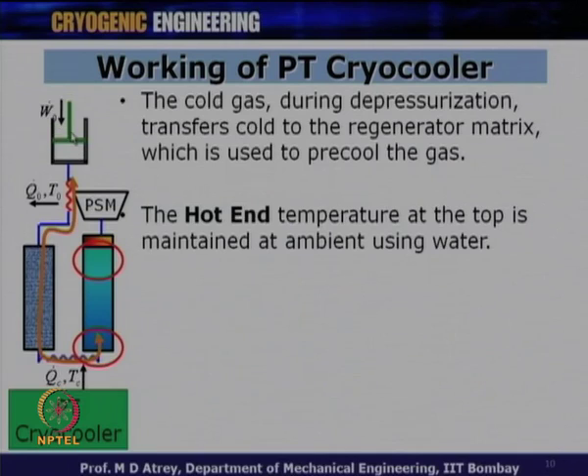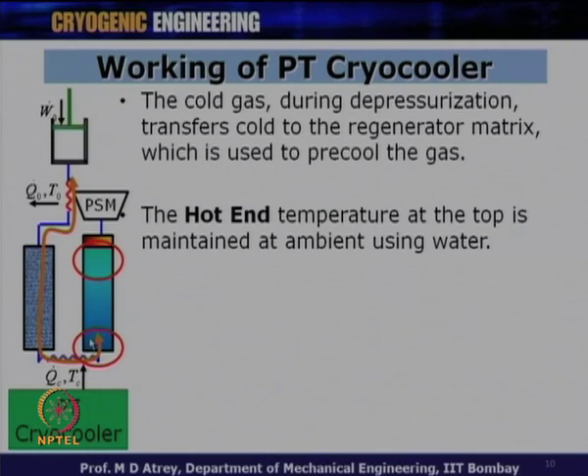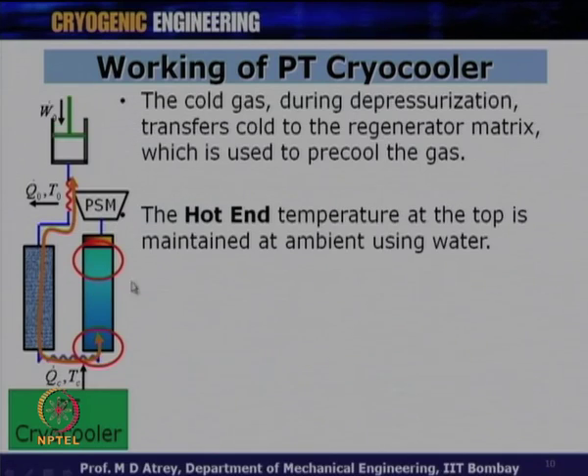This is how the pulse tube cooler works. The pulse tube cooler compresses gas and sets up a temperature gradient across the length of the pulse tube. During depressurization, the gas goes back; the hot end is always maintained at ambient temperature. Thereby, the lower end temperature starts going down — how much it goes down depends on the capacity of the regenerator matrix material to store heat. The major difference is no displacer, and the oscillating gas flow sets up the temperature gradient.